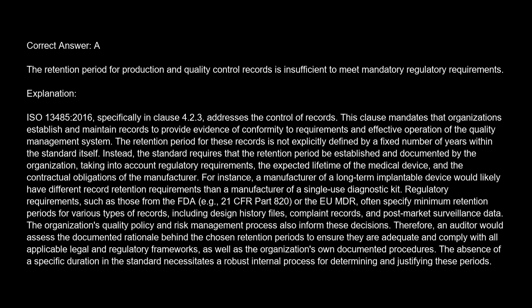For instance, a manufacturer of a long-term implantable device would likely have different record retention requirements than a manufacturer of a single-use diagnostic kit. Regulatory requirements such as those from the FDA, e.g. 21 CFR Part 820, or the EU MDR often specify minimum retention periods for various types of records, including design history files, complaint records, and post-market surveillance data. The organization's quality policy and risk management process also inform these decisions.